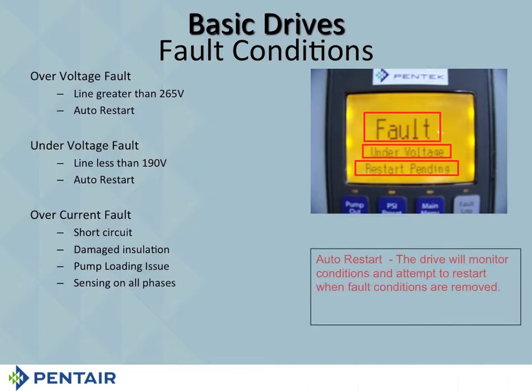Auto restart means the drive monitors the condition and attempts to restart when the fault conditions are removed. The next one that's there is overcurrent. And you'll notice overcurrent can be a problem of short circuit, damaged insulation, and yes, I've seen that one before. It can be pump loading issues, or it could be sensing on all phases. And so that's going to cause a problem, and it's going to be called overcurrent.